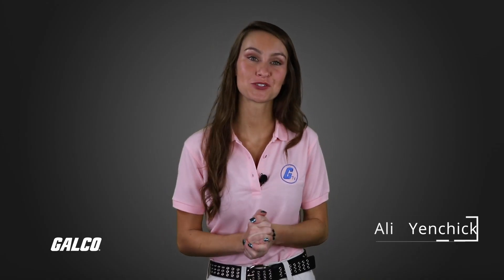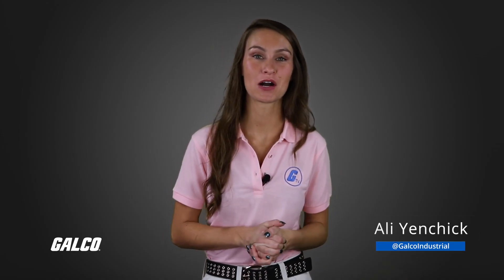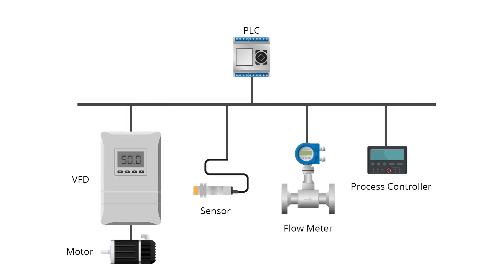Fieldbus is a group of industrial network protocols used in real-time distributed control systems. It allows multiple instruments to connect to one communication point at the same time, typically at the controller level. This eliminates the need for each device to have its own communication point with a controller, reducing the length and number of cables required in the network.